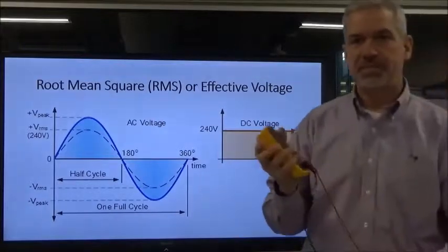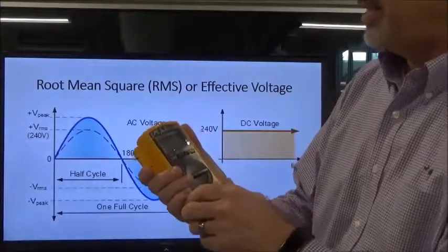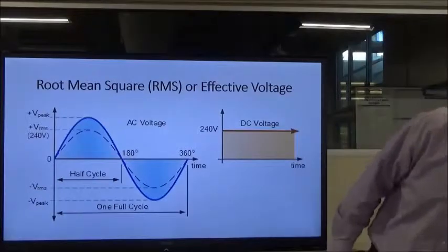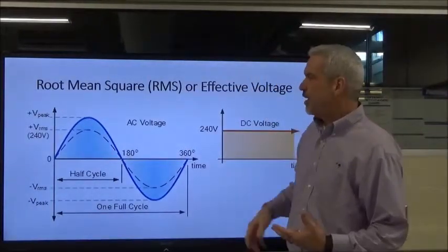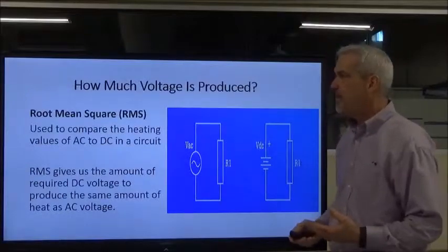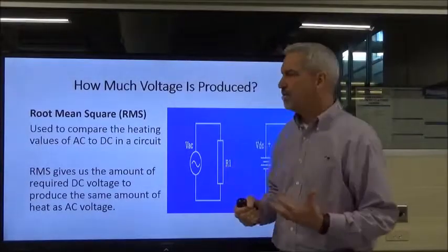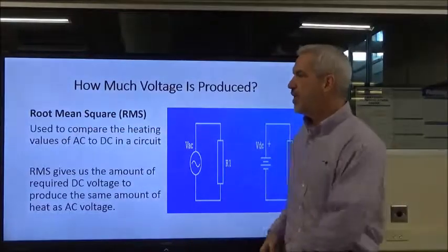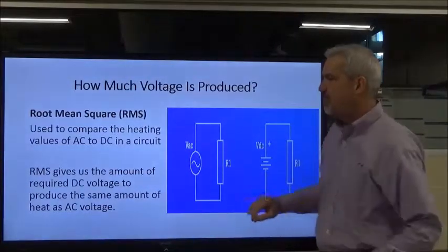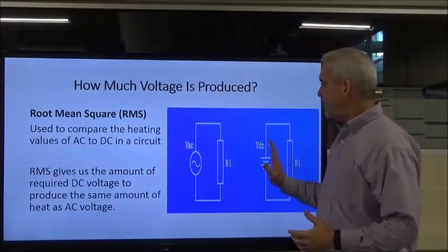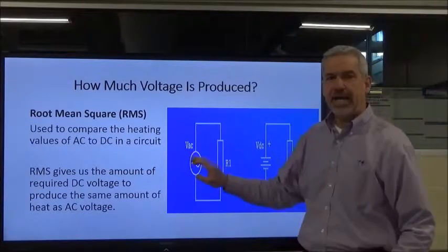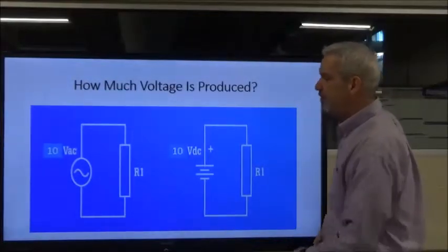Even with our Fluke meter here, it says right here: true RMS meter. That means it's measuring true RMS, not peak-to-peak or peak voltage. So our true RMS and our effective voltage are very different from peak-to-peak and peak voltage. When I'm talking about root-mean-square, this was developed so that we could compare the heat values of an AC circuit to a DC circuit. The RMS gives us the amount of voltage that needs to be applied to a DC circuit to create the same heat value as in the same AC circuit.